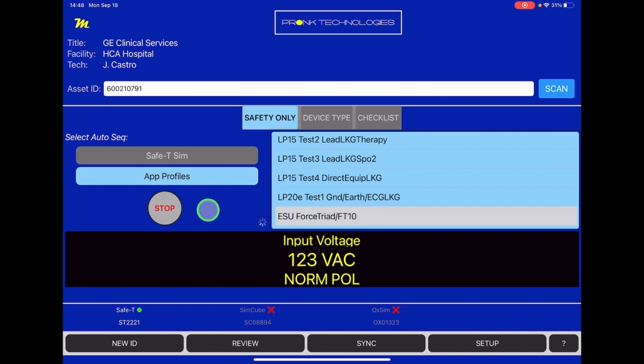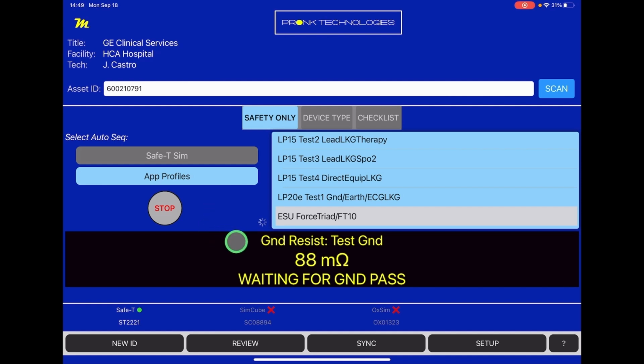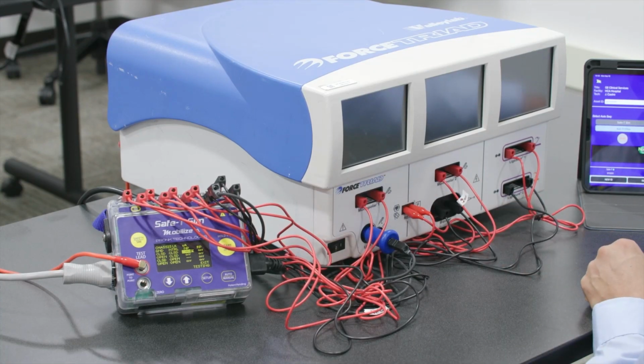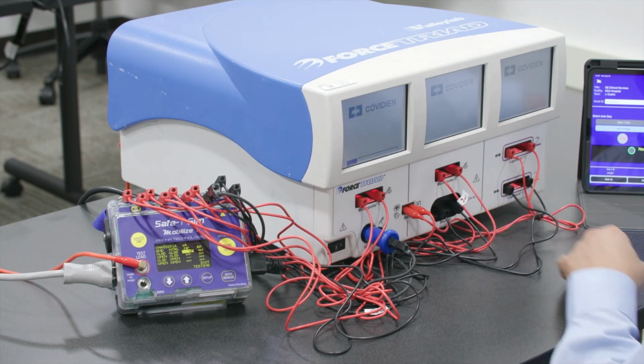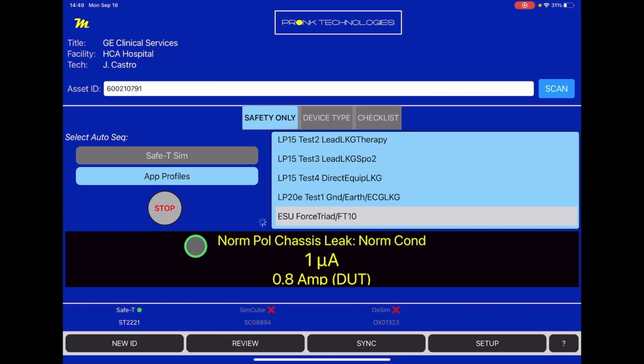The safety analyzer will automatically start to perform that test, and we'll see here in the lower window via the Mobilize app that we're running a ground resistance test, and we're going to start all the other tests. So we've turned on the ESU analyzer. It's going to take some time to boot up. That's why these tests will take a little longer to run, giving the analyzer time to boot up.